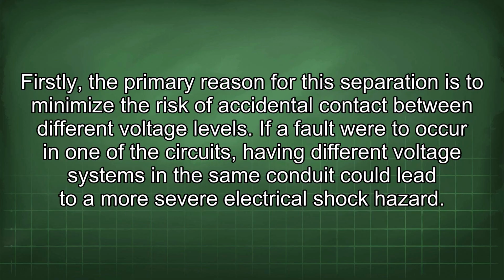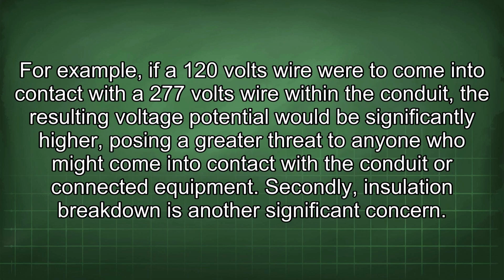Firstly, the primary reason for this separation is to minimize the risk of accidental contact between different voltage levels. If a fault were to occur in one of the circuits, having different voltage systems in the same conduit could lead to a more severe electrical shock hazard. For example, if a 120 volts wire were to come into contact with a 277 volt wire within the conduit, the resulting voltage potential would be significantly higher, posing a greater threat to anyone who might come into contact with the conduit or connected equipment.